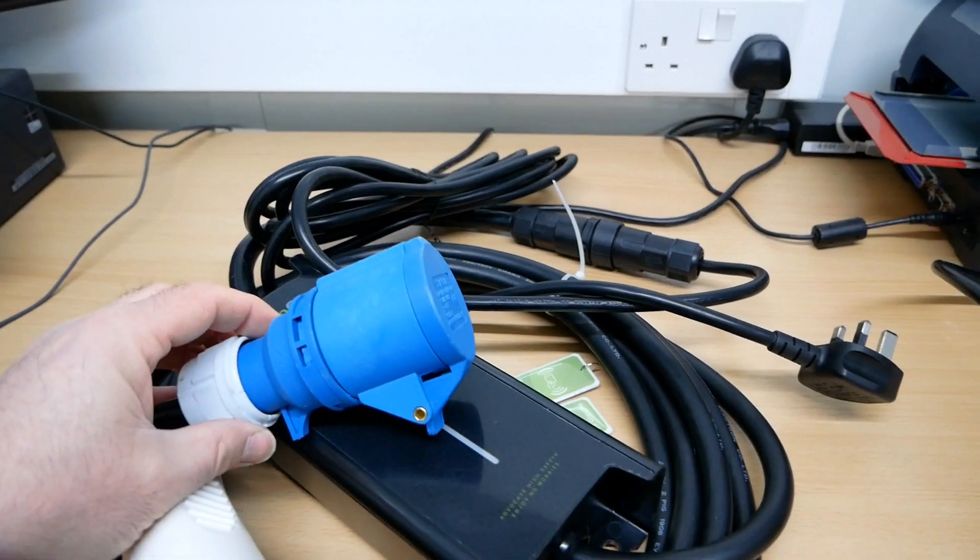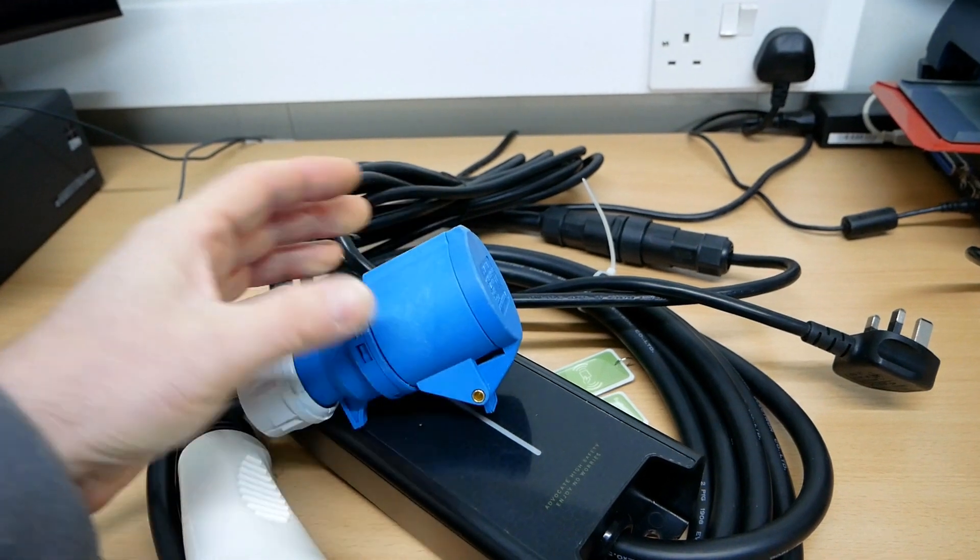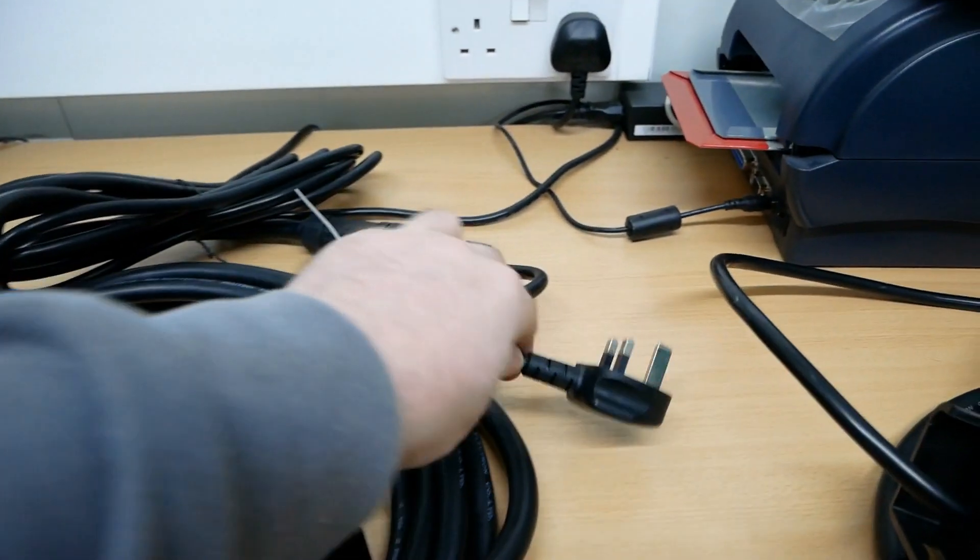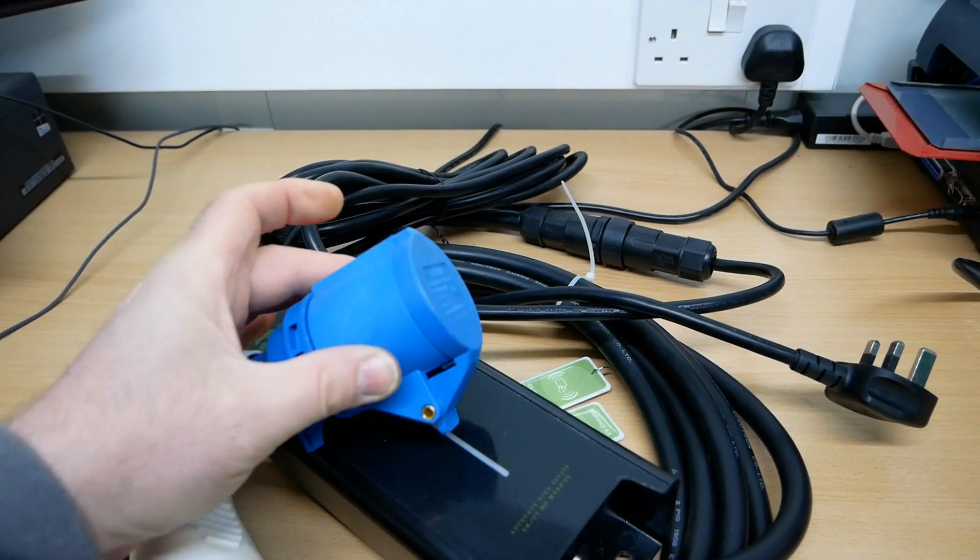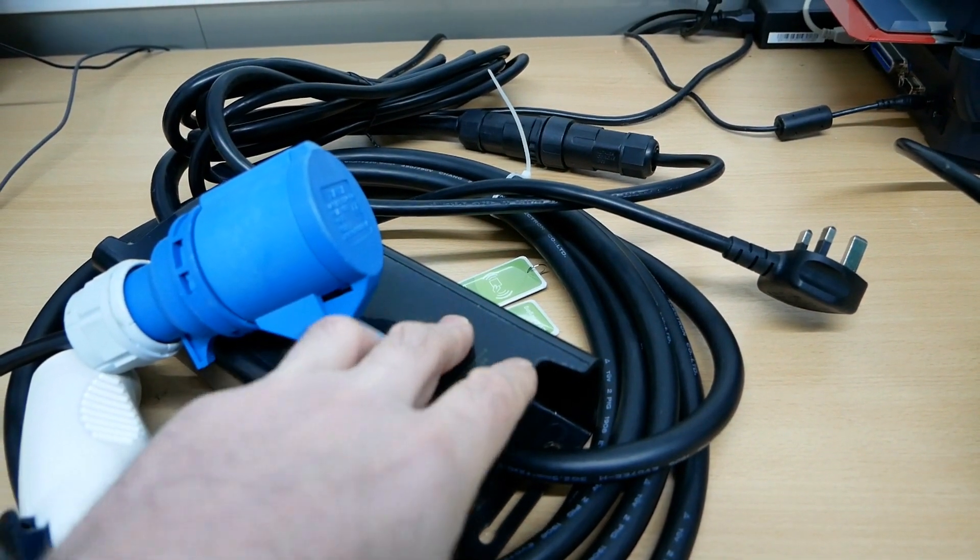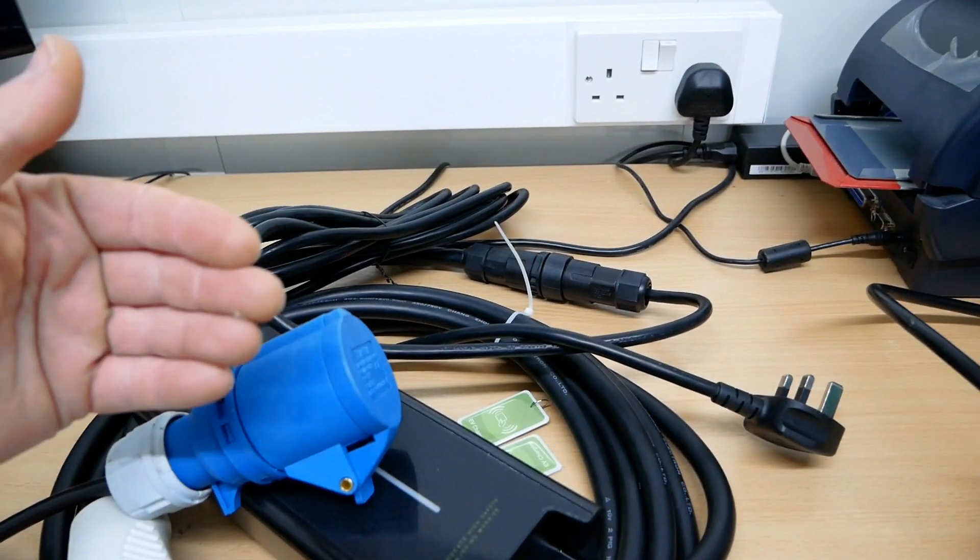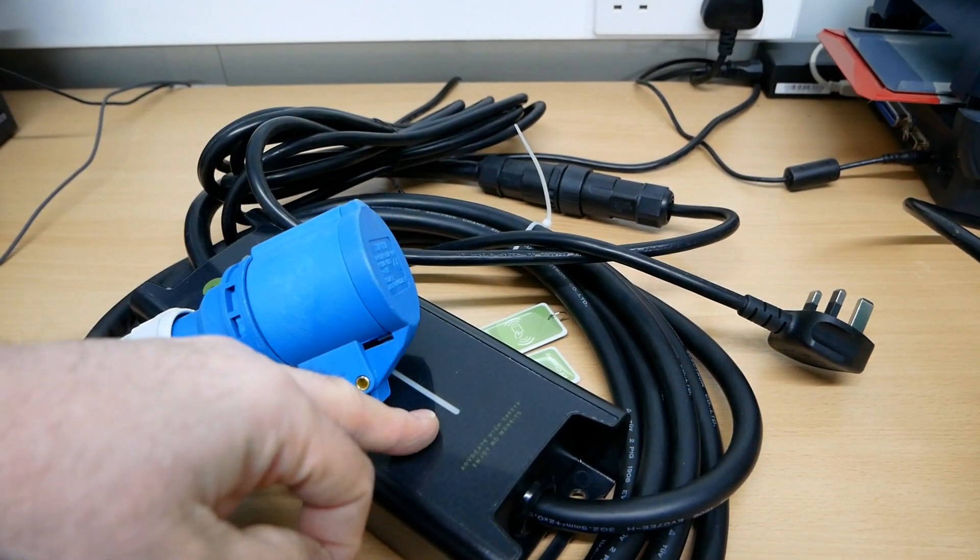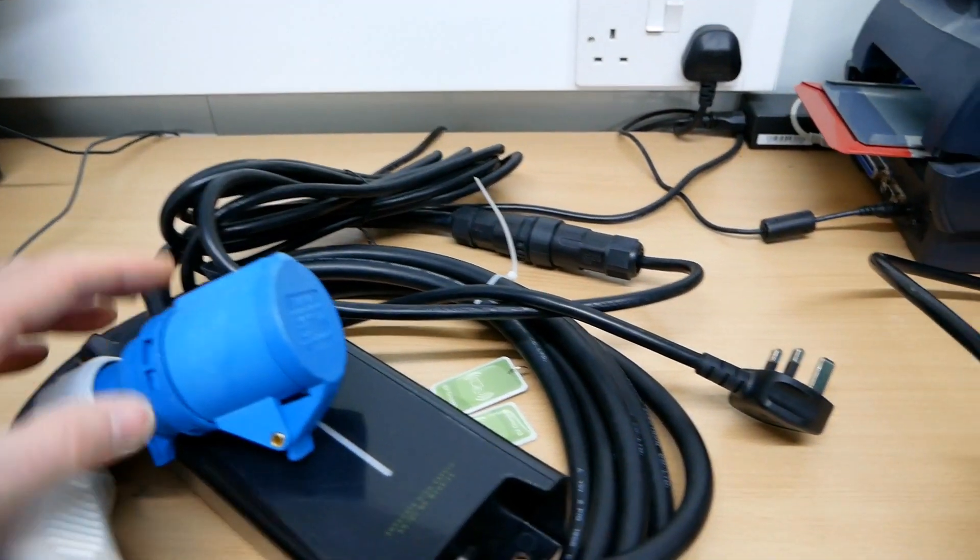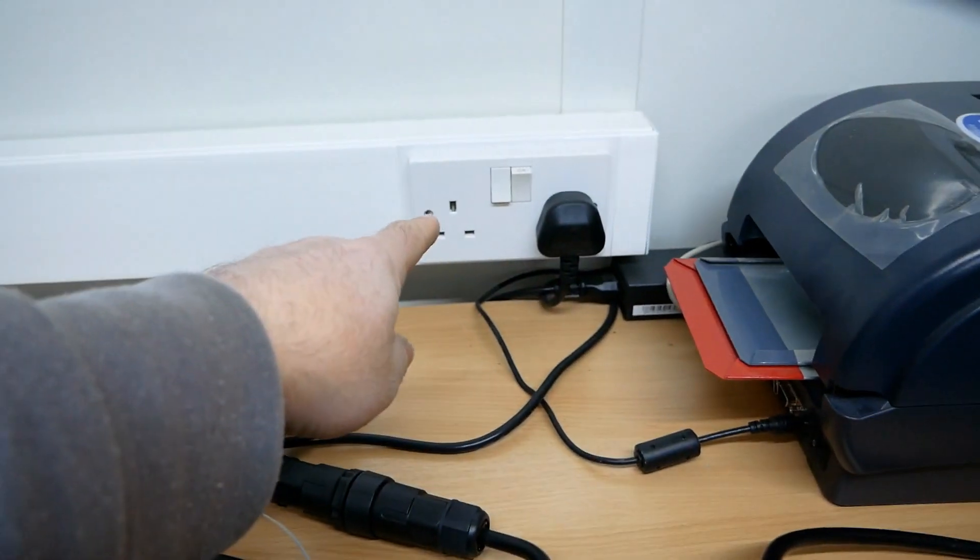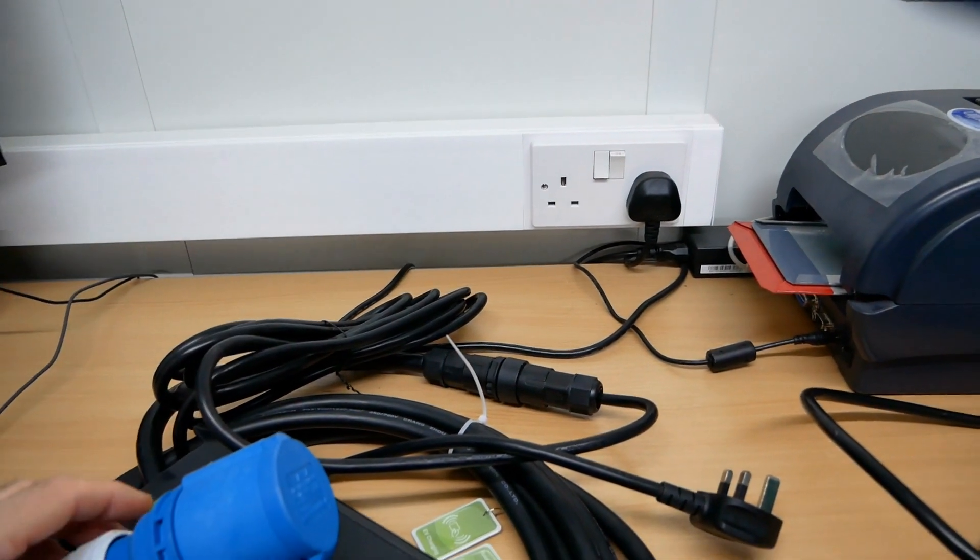I'll just mention the commando sockets. These commando sockets are often what caravaners use if you've put a supply on the outside of your house. The UK plugs are 13 amp maximum. If you want to go higher, you go commando, and these are 16 or 32 amp versions. If you've got a 16 amp granny cable, you could have a commando socket on the end and have a dedicated commando supply and charge your car at 16 amp with one of these, as long as you use commando plugs and sockets and not 13 amp plugs and sockets and a 13 amp ring main. You need a dedicated 16 or 32 amp supply.